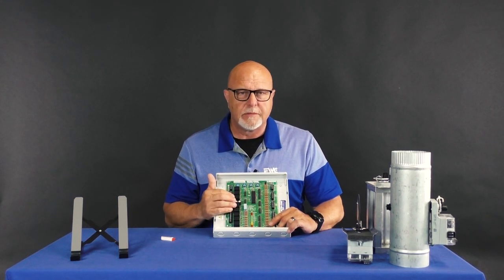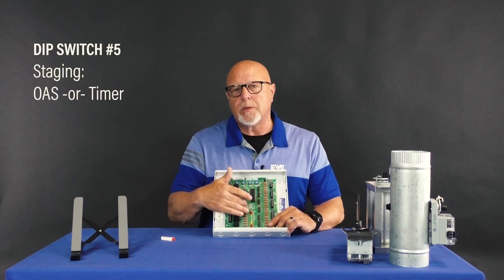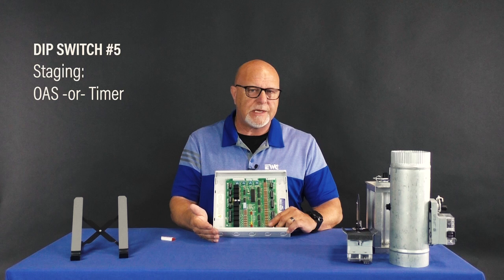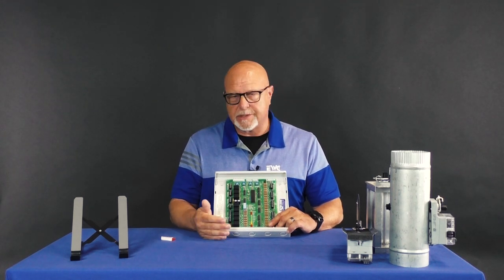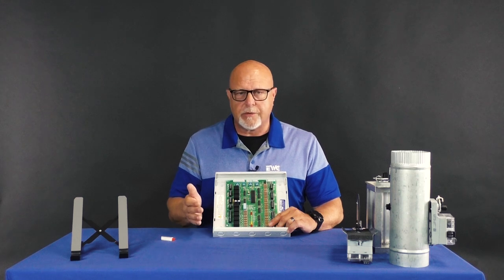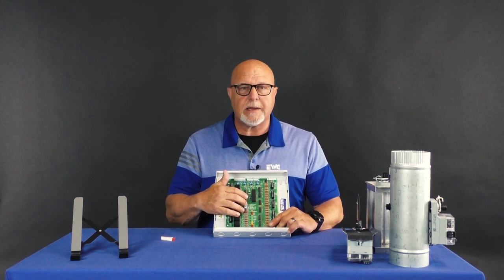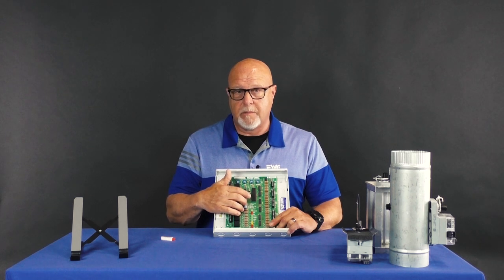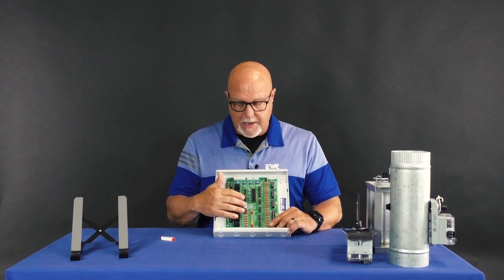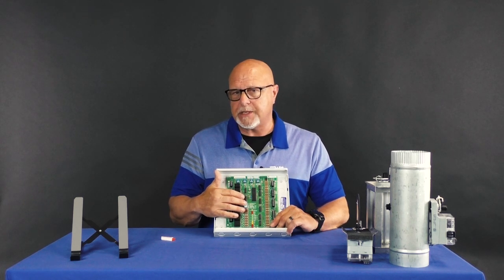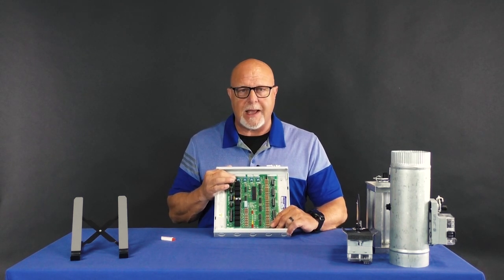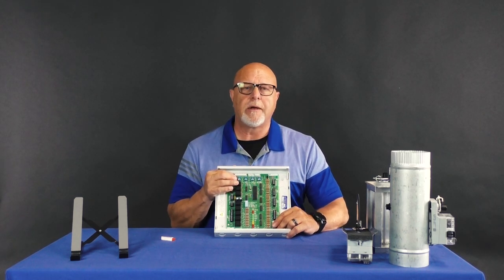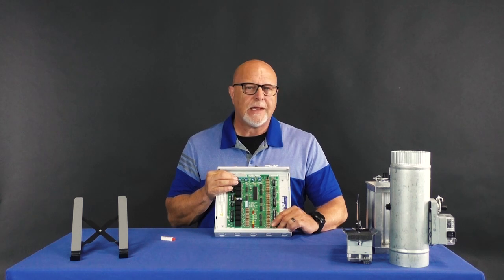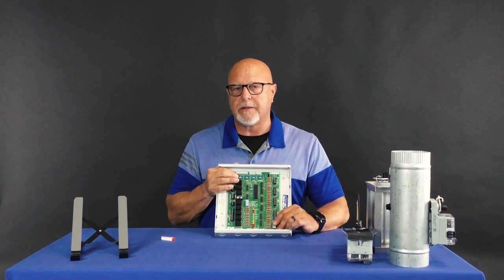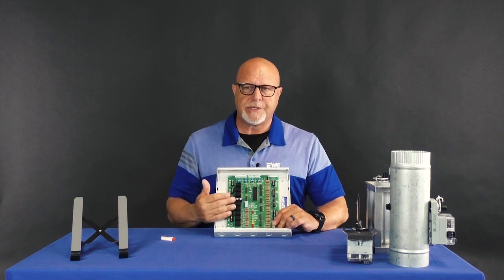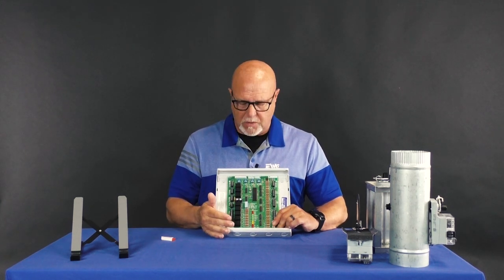So the fifth dip switch that I will talk about is, how do you want to stage the equipment? Now, obviously, if your system is a single stage heat, single stage cool, there will be no staging. This is for a multi-stage 2 heat or 3 heat, 2 cool system. You would select either time, which is the normal way or out of the box setting. This is your timing staging, meaning if you had set this dip switch at 14 minutes, this will allow first stage to operate up to 14 minutes. If at 14 minutes it has not satisfied the thermostat, that will allow the board to transition into its next stage or higher stage of heating or cooling.